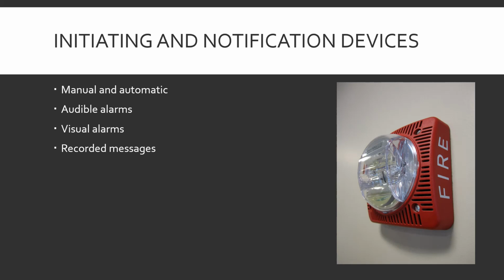In notification devices, the audible and visible alarms. That's the big strobe light, the annoying buzzing. If you've ever been around when one of those wall-mounted buzzing ones, the modern ones, goes off, you can feel it. That is designed that way, in your chest, like you're at a concert. That's another notification device, so if someone is blind and deaf, they can feel it. It's trying to provide all the opportunities to notify people that the alarm's going off.